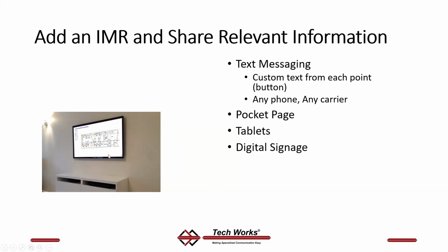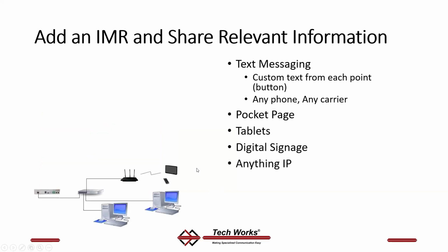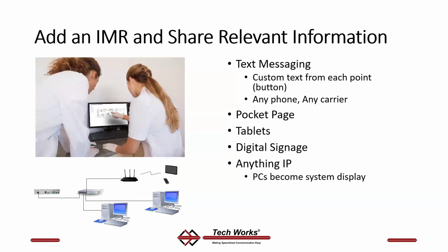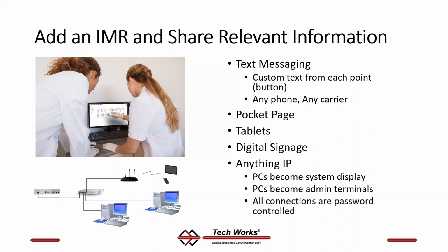Those lights, those buttons in a clinic call system or a nurse call system all show up on the wall and tell you where everybody is. Basically, the IMR takes the TechWorks product and connects it to anything IP so that PCs become not only system displays, but also admin workstation terminals. This is all controlled through how you set up your users. Any user, through their credentials and their password, has a unique display to that user and has access to only those items that they're authorized to have.